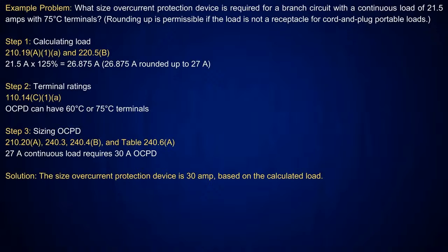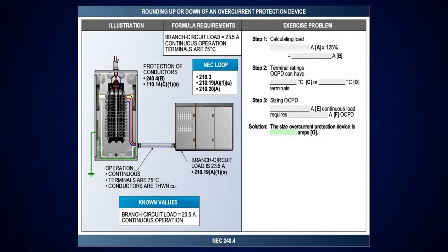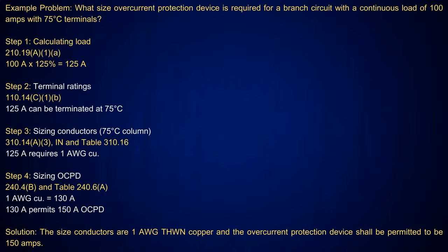Well, all I'm going to do here, if it's continuous, I take it at 125%. So 21.5 amps times 125% is 26.8. We're just going to round it up to 27 amps. What is the next size above that for table 240.6? That's a 30 amp overcurrent protection device. Okay. Right. And then you get your illustration here. Same calculation. I've got 23.5 amps. It's continuous. I take it at 125% and then size my overcurrent protection device for that.